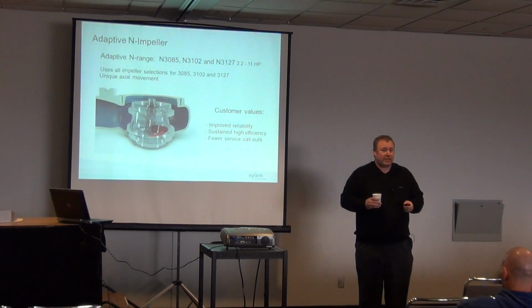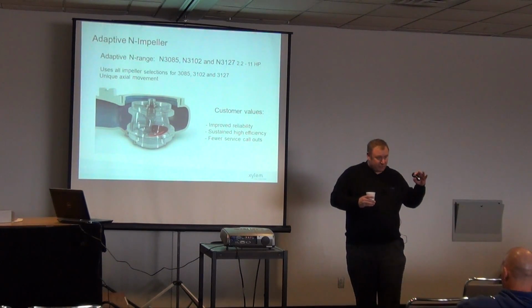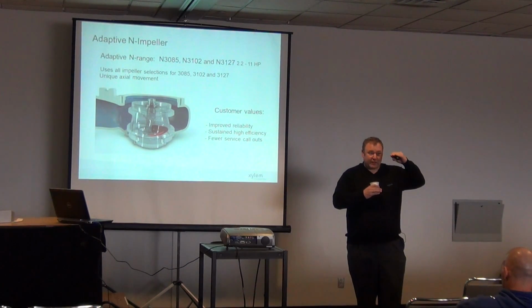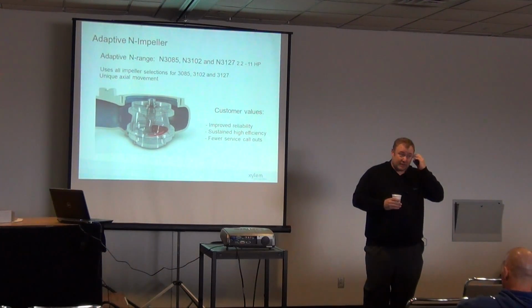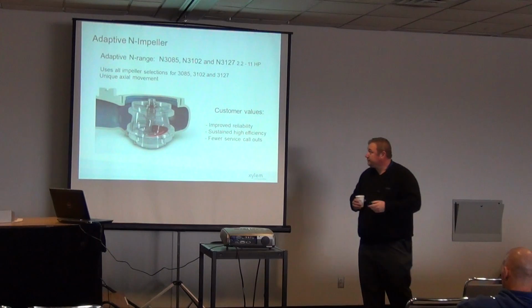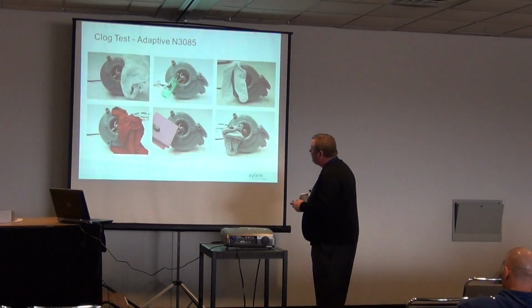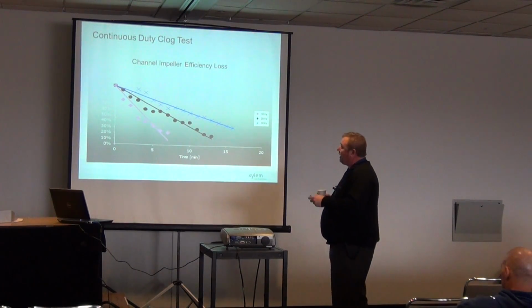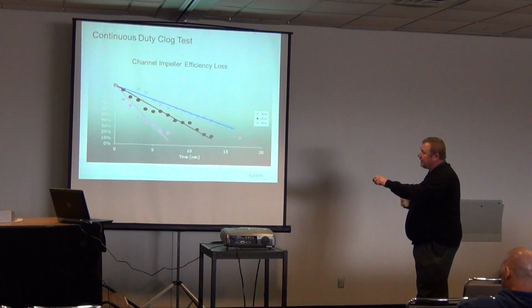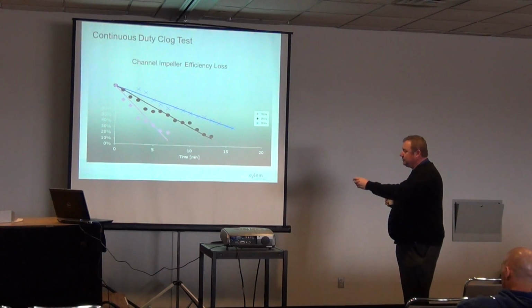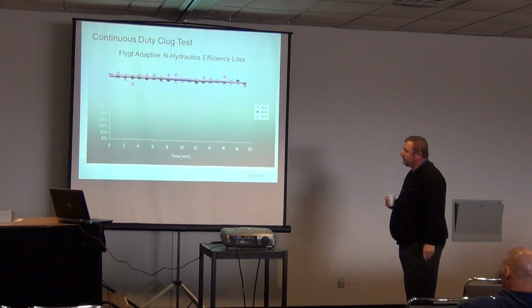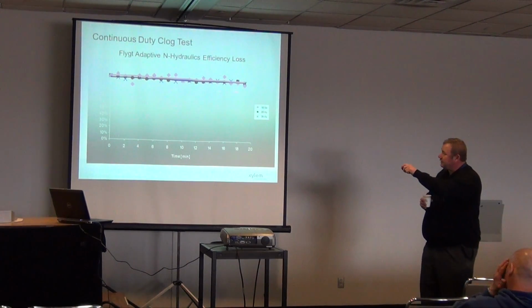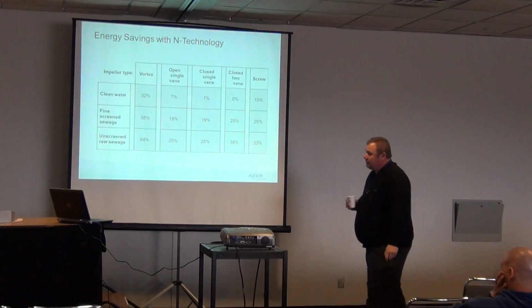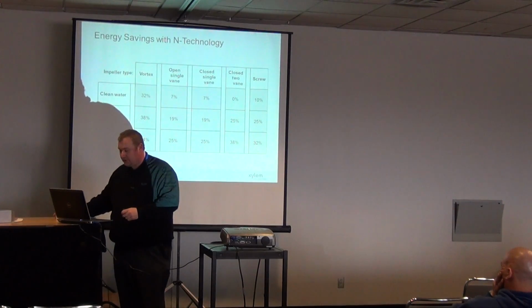So anytime you have a piece of rotating equipment and you're spinning it, and a piece of material comes into that pump and hits it, it creates shock. By moving that impeller up a little bit, it shortens that shaft overhang length, saving and lengthening the time of your seals and bearings and wear and tear on those. These were some of the tests that were done, talking about channel impeller efficiency loss over time and that soft clogging phenomenon that you see. That's been done, and it's been done in all kinds of pumps in R&D, and that's the kind of efficiency loss that we see in the end. None. It just sustains over time. So with that said, I'm going to jump to the controller portion.